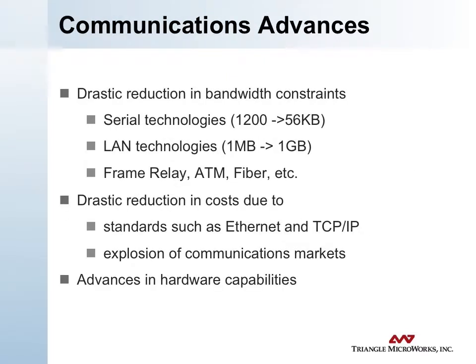Since these SCADA protocols were developed, we've had some really radical changes in bandwidth constraints. Serial technologies have moved from what were typically 1200 baud links some years ago to a minimum of 56 kilobaud. LAN technologies have gone from the megabyte range to the gigabyte range, and we've developed new technologies like frame relay that really change the picture for substation communications.